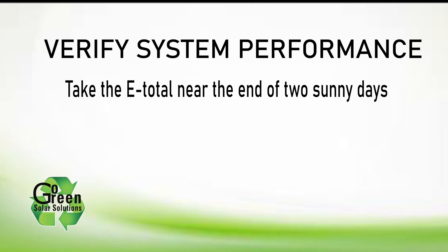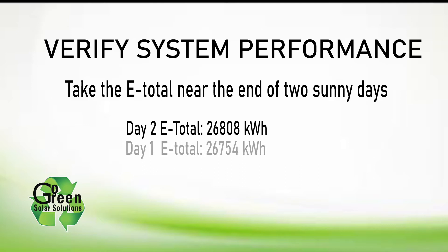One simple way to verify the solar system performance is to write down the E-total on two consecutive cloudless, sunny days at sunset. Subtract the first day's total from the second day's total and you can see how many kilowatt hours your system has produced over the 24-hour period.